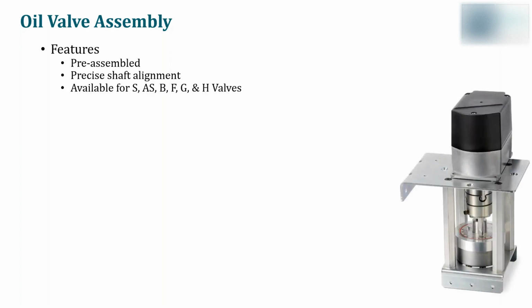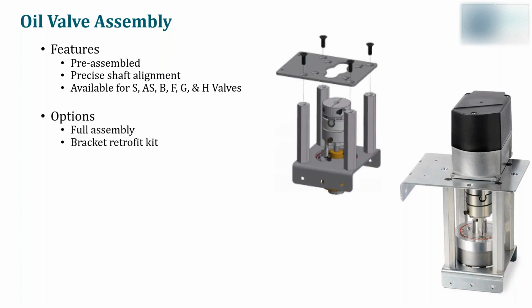Now, just like the gas valve assembly, Siemens offers a complete assembly for the Hauck oil valve. Some of the features include it's pre-assembled, it has precise shaft alignment, and it is available for the S, AS, B, F, G, and H valves. Options include you could purchase either the full assembly or a bracket retrofit kit, but it's very important to let us know which valve you currently have on there, because depending on which valve it is, they do have different brackets. In terms of sizing, you can use the Hauck capacity oil tables.